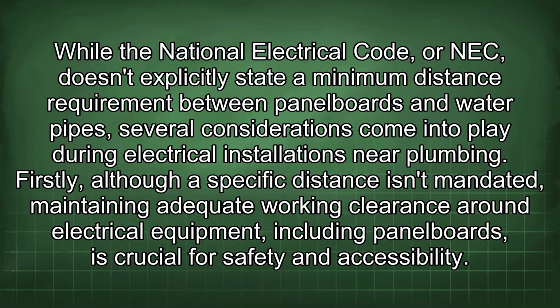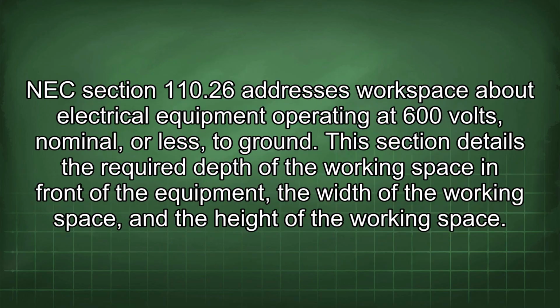While the National Electrical Code, or NEC, doesn't explicitly state a minimum distance requirement between panel boards and water pipes, several considerations come into play during electrical installations near plumbing. Firstly, although a specific distance isn't mandated, maintaining adequate working clearance around electrical equipment, including panel boards, is crucial for safety and accessibility. NEC Section 110.26 addresses workspace about electrical equipment operating at 600 volts, nominal or less, to ground.